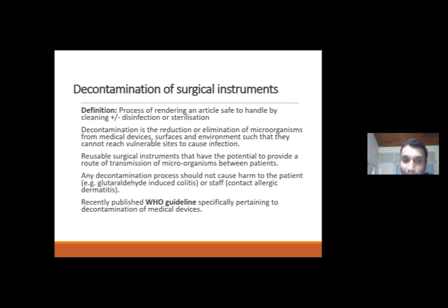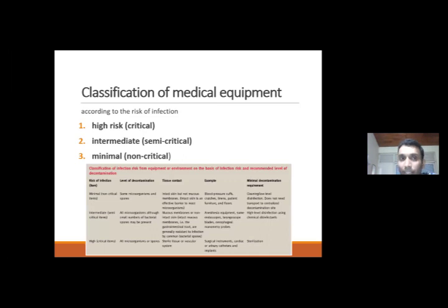Recently the WHO published guidelines specifically pertaining to the decontamination of medical devices. We can classify medical equipment according to the risk of infection: high risk, intermediate risk, and minimal risk. The minimal risk are instruments used on intact skin, such as the blood pressure cuff as well as the stethoscope. We can use just cleaning for this.